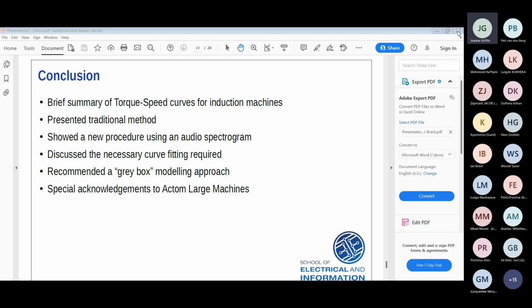In the background research, there's quite a lot of work looking at using the saliency of the machine to work out the speed versus time trace hidden in a current harmonic. As a machine is rotating and the air gap is not uniform, it's obviously going to create other harmonics which are evident in the current waveform. You can pull out the speed versus time trace from the current waveform and do all of this. So instead of using an audio signal, like what I've done, you could use a current signal, pull out a particular harmonic due to the saliency, and do the same thing with the polyphase power. The software for that is already there, it's done in much.